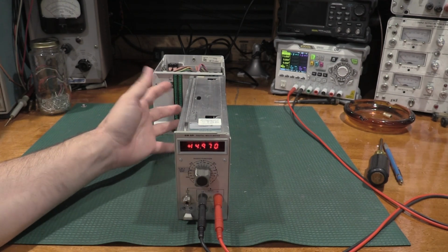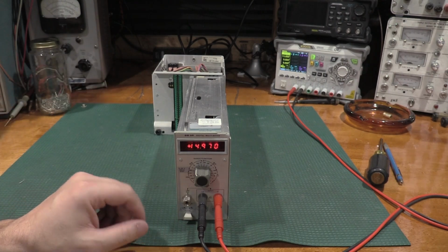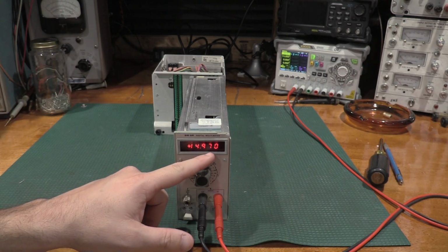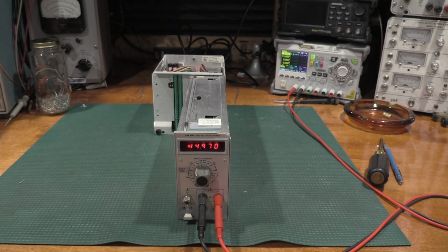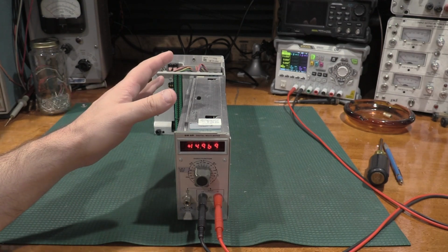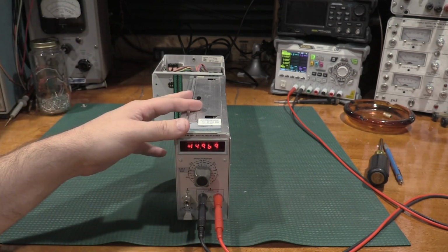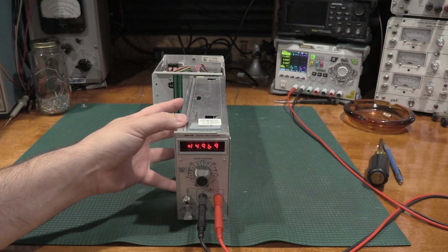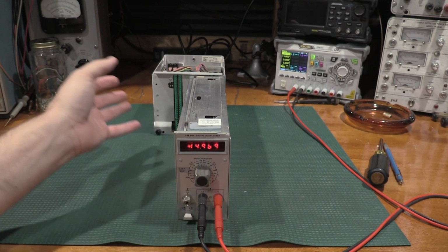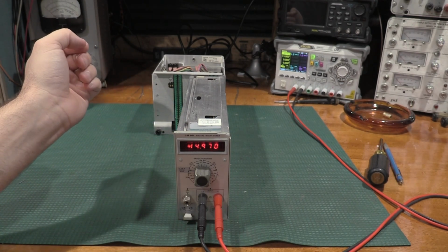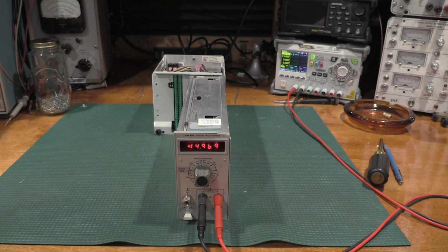But none of this gear's warmed up. It's been on for 30 seconds, so I expect all of this to change and some things to drift around for a little bit. So we'll wait on the 7.5 to warm up. I'm going to get in, service the contacts and the switches real fast, and then we will just kind of spot check the alignment.